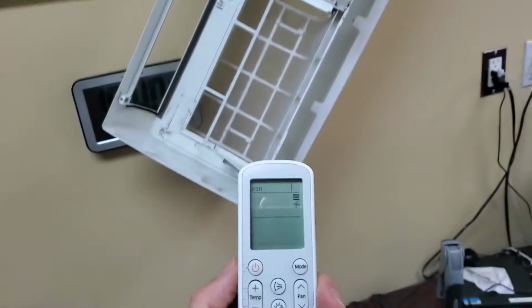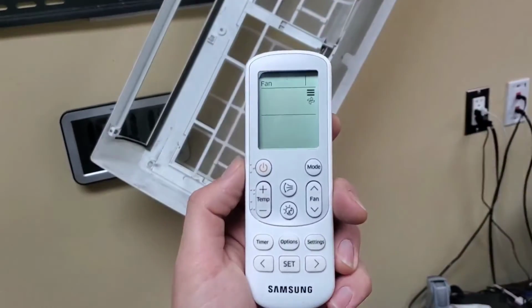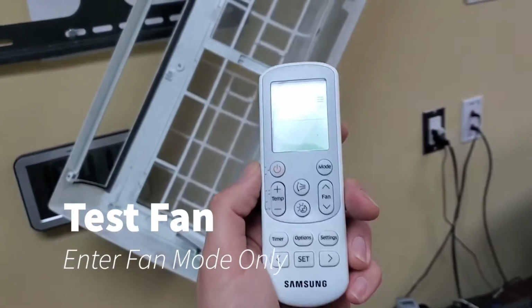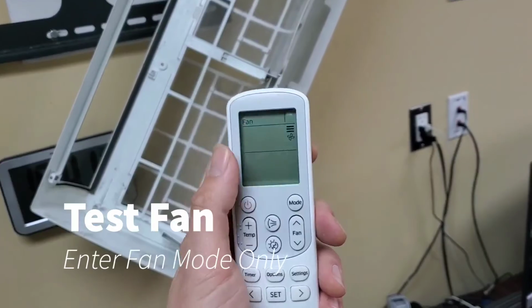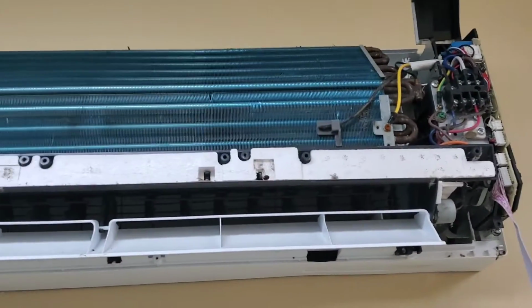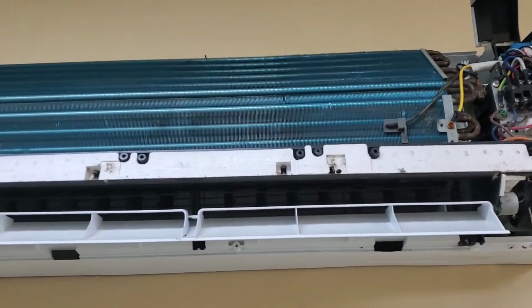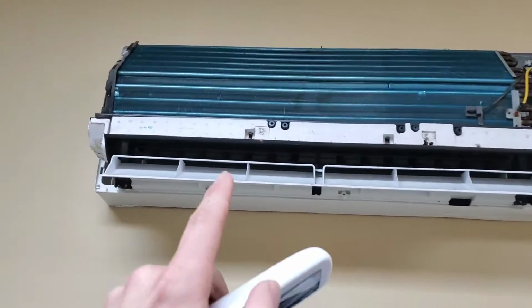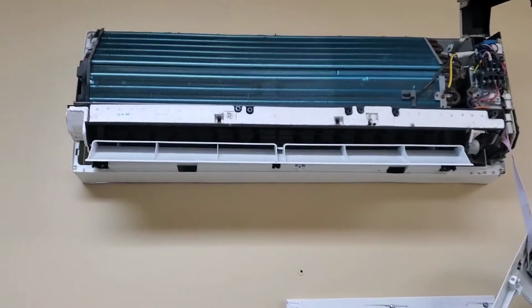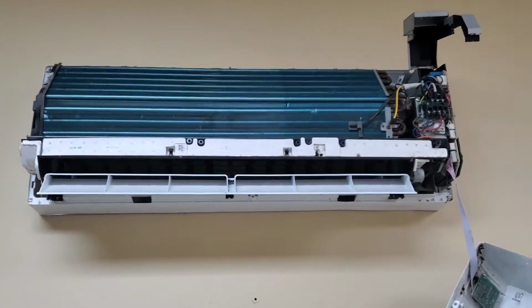Before I take the fan cover completely down, I'm actually going to use the display, the receiver, and my transmitter here, and I'm going to put the fan on high speed. Since I put the fan on high speed, before the coil was freezing, now it's not. Looks like with the indoor fan motor, there's actually probably nothing wrong with that, but there could be a problem with the board. So let's do some further diagnostics to figure out what the problem is.